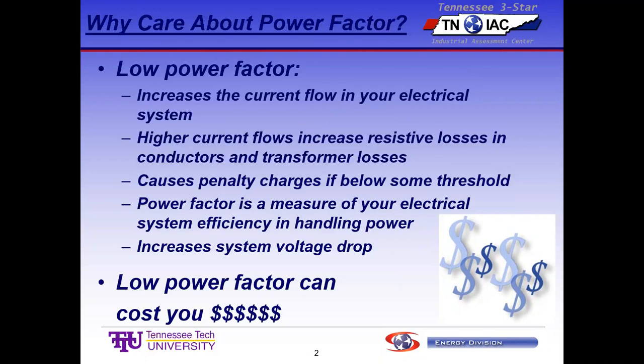Okay, higher current flows, and if you put more current through a wire, you have more resistive loss, I squared R. Whatever the resistivity of the wire is, current squared times resistivity in correct units will give you power loss for just flowing the current through the wire. So power factor goes down, current goes up, I squared R losses have to go up proportionately.